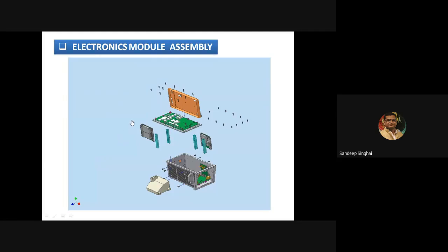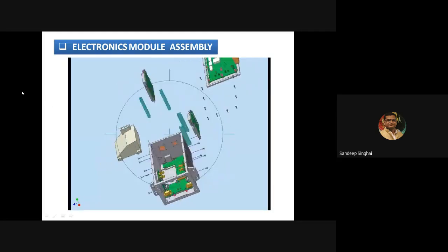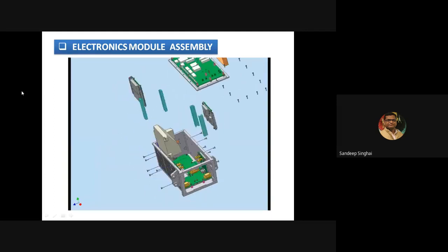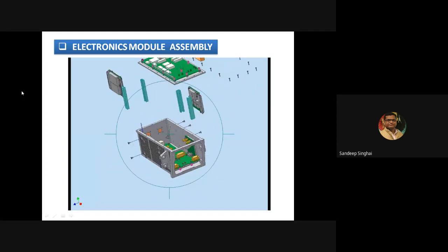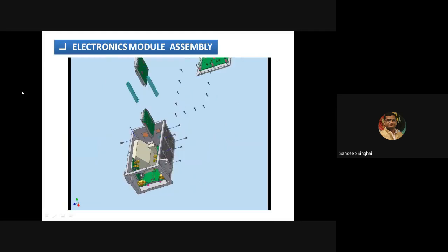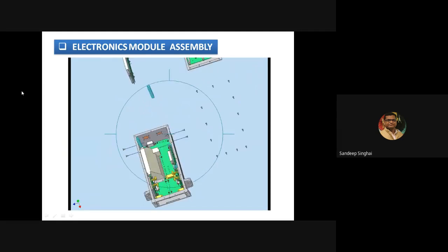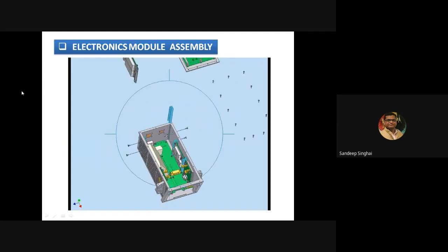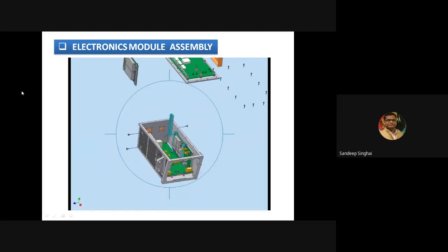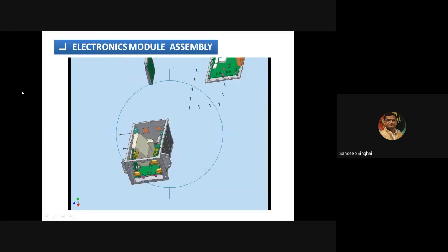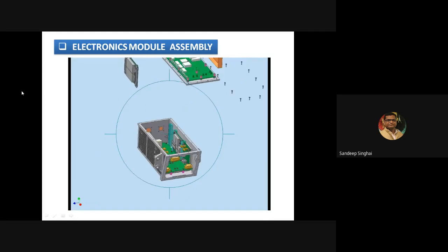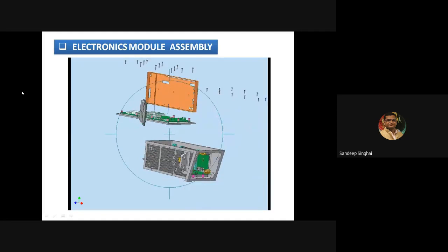Another CAD model I just want to show you to highlight how tightly things are packed, and within these parameters you have to pass all the tests regarding environmental, thermal and vibrational requirements. So things need to be really sturdy, and thermal is a big issue. Thermal management we have been doing very nicely. Our design is without a fan, which is a remarkable achievement, and we were the pioneers in this domain. Otherwise, prior to CSIO, globally, the HUDs used to have a fan for cooling purposes.